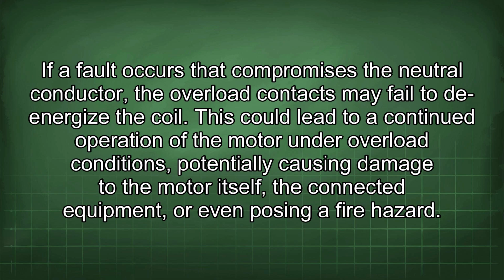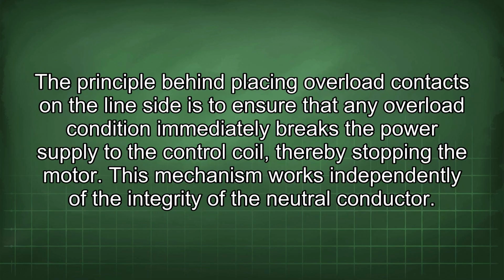This could lead to a continued operation of the motor under overload conditions, potentially causing damage to the motor itself, the connected equipment, or even posing a fire hazard. The principle behind placing overload contacts on the line side is to ensure that any overload condition immediately breaks the power supply to the control coil, thereby stopping the motor. This mechanism works independently of the integrity of the neutral conductor.